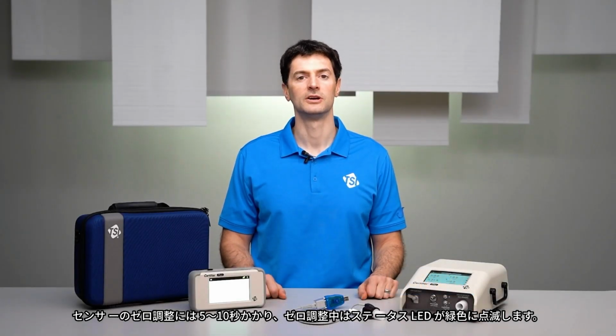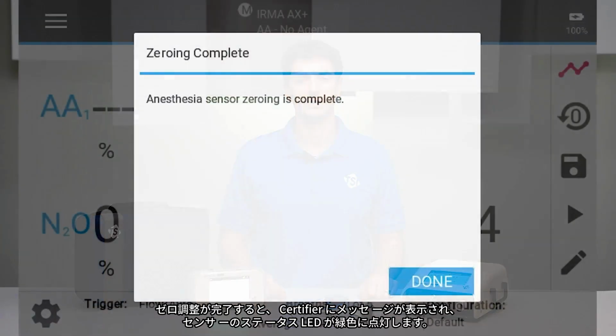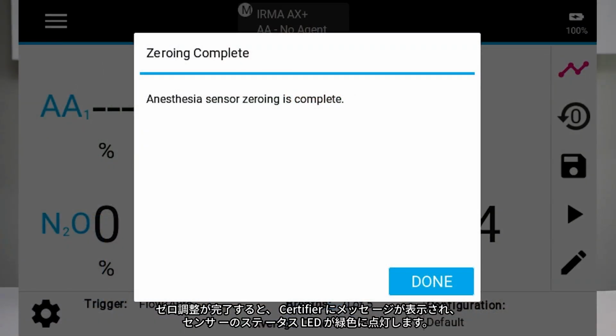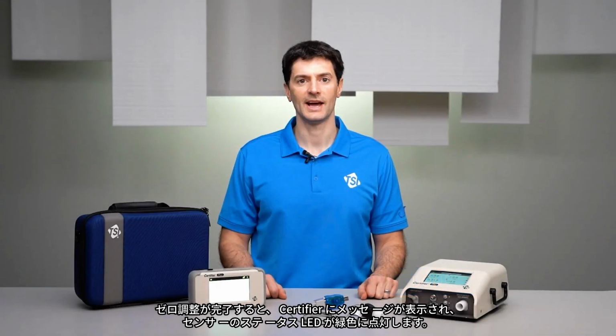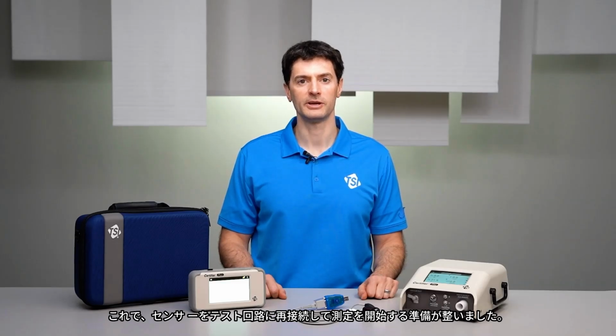in process. Once zeroing has completed, a message will be displayed on the Certifier, and the status LED on the sensor will illuminate solid green. You are now ready to reconnect the sensor to your test circuit and begin taking measurements.